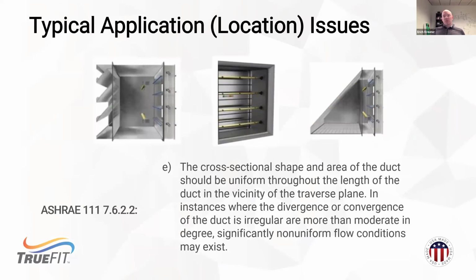Matt mentioned as an industry, we typically put the technology where we need to. A lot of times it's inside louvers and hoods and things like that. So these pictures here, I would say are pretty representative. Most people would agree that they've seen these type of sensors installed in these locations, which again, turbulent airflow. If a balancer were to come in and take a measurement, ASHRAE says in 111 that if you don't have accurate measurements, you can't use a laminar flow-based measurement, and you need to use something they call the temperature ratio equation. And we'll talk about why that's important here in a minute. But know that a balancer couldn't take a measurement accurately in these situations most of the time.